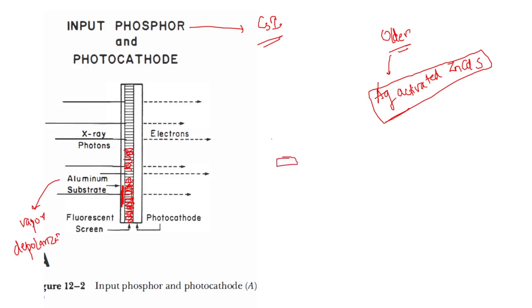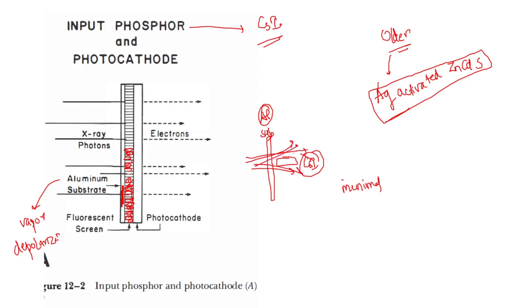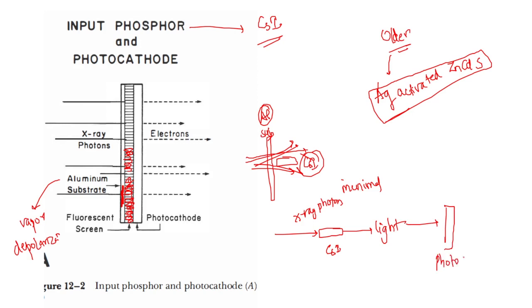Because the CsI crystals are perpendicular to the aluminum substrate, there is minimal lateral light diffusion. These needle-shaped crystals absorb the X-ray photon and produce light. The CsI crystals absorb the X-ray photon, produce light, and this light is transmitted to the photocathode.